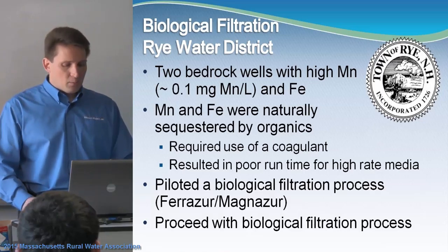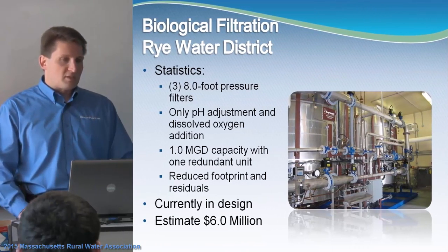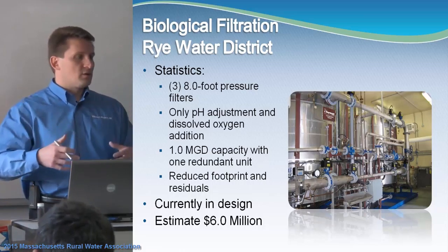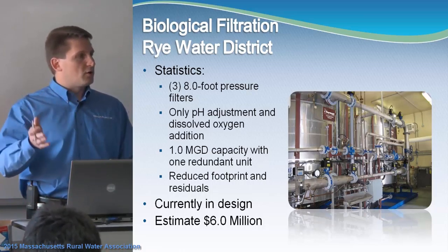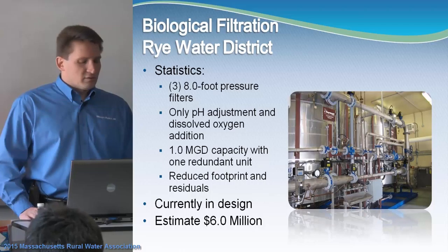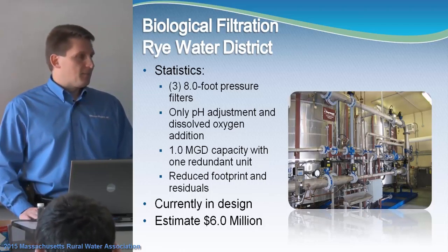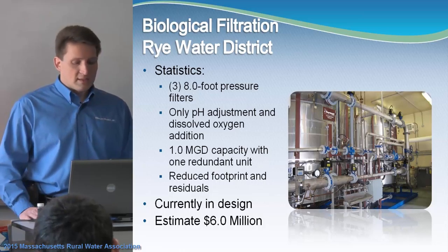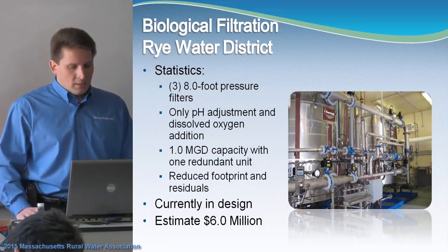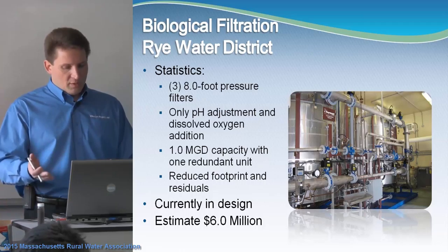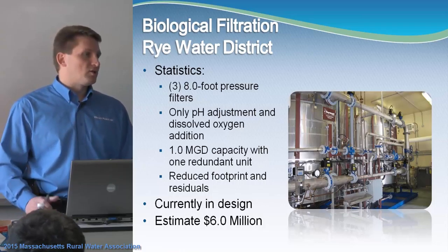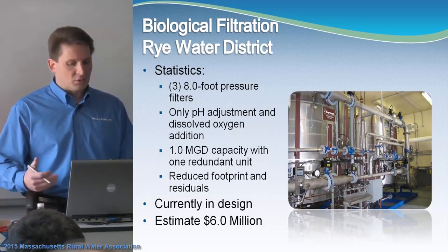At that point they decided to look at the biological process — referred to as the Ferrazur/Magnazur process. From what I understand, it's a media that only needs a stable pH and oxygen to allow naturally occurring bacteria from the wells — which eat iron and manganese and form slime layers — to remove the iron and manganese from the water. Following successful piloting, they decided to proceed with that process. The design would be three 8-foot diameter pressure filters needing only pH adjustment and dissolved oxygen, with a capacity of 1.0 MGD and one redundant unit. The process backwashes less frequently, reducing residuals. The facility is currently in design at an estimated cost of about $6 million.